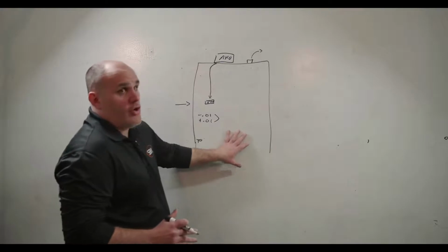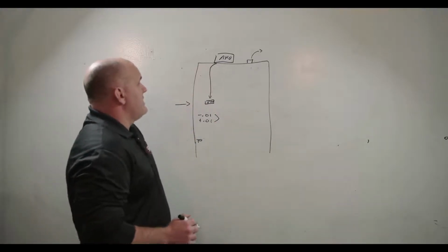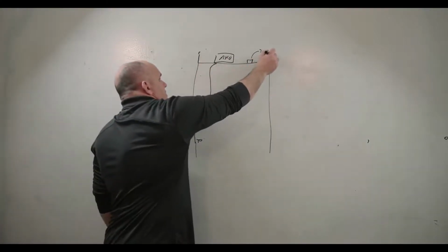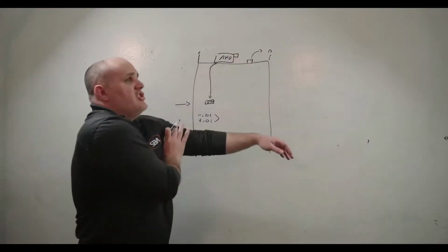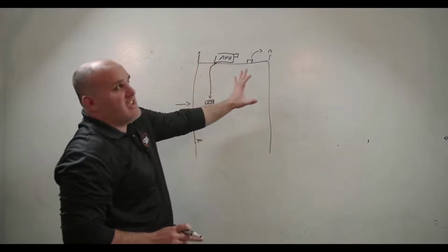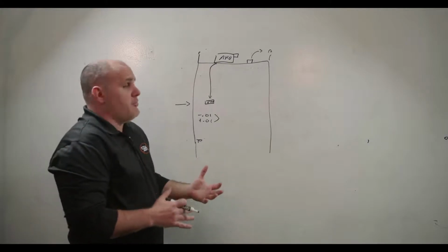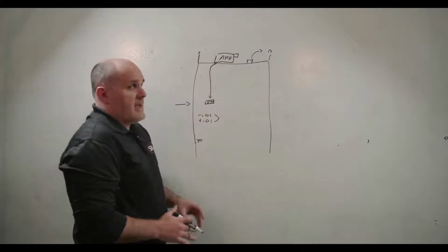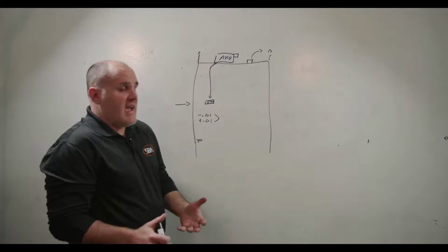So that's for internal building static measurement. For external building static measurement, typically we'll see a pressure sensor here and a pressure sensor here, or we'll see a pressure sensor on the actual AHU. I personally like having it on the buildings, and I like to do an averaging effect. That way I account for the effect of wind on that pressure signal. So that's for the outside pressure and then inside pressure, because we need to know the two so that we can tell if we're positive or negative.